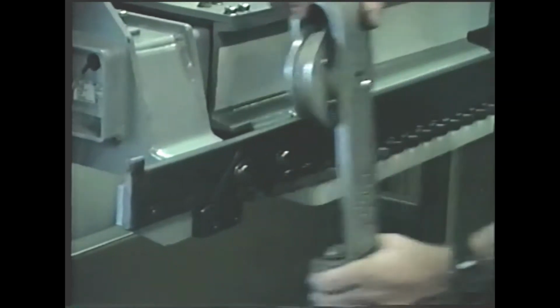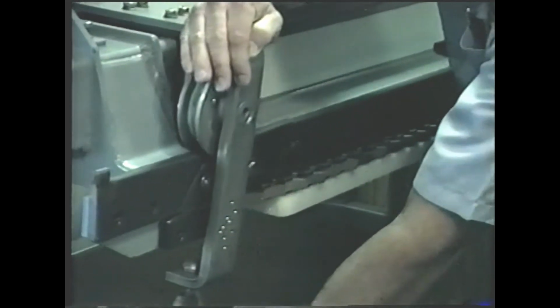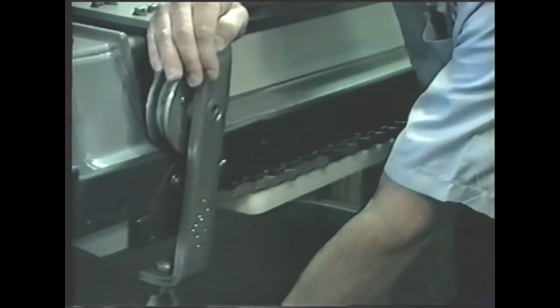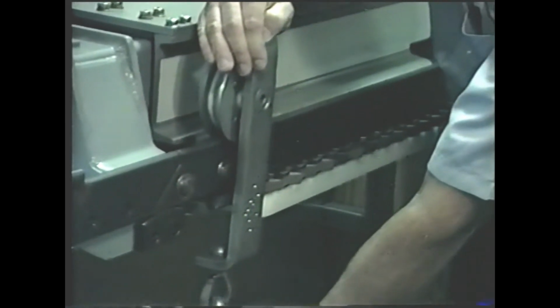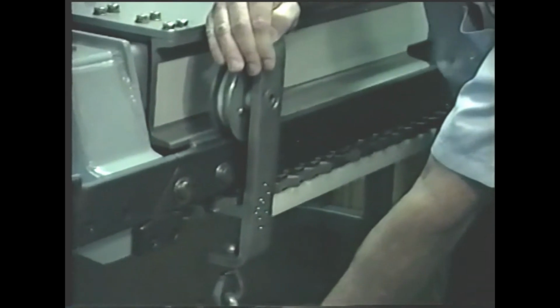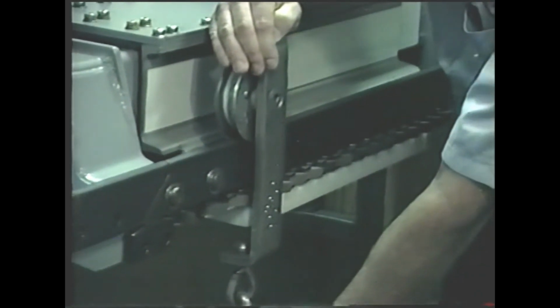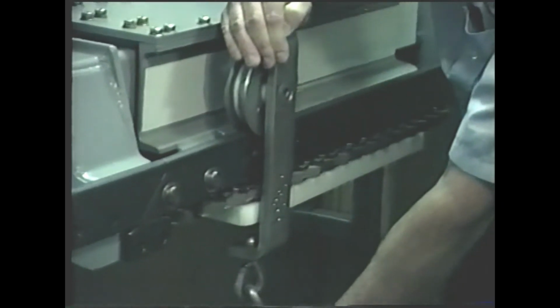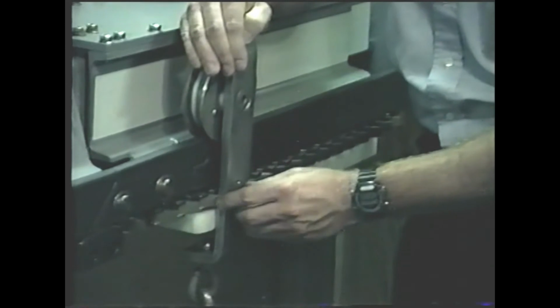So essentially what happens is as the trolley rolls onto the transition rail, initially, approximately 10% of the trolley load is applied to the scale. As it rolls across the transition rail, this is gradually increased until 100% is obtained approximately in this area here. Shortly thereafter, the trolley is caught up to by our drive chain.